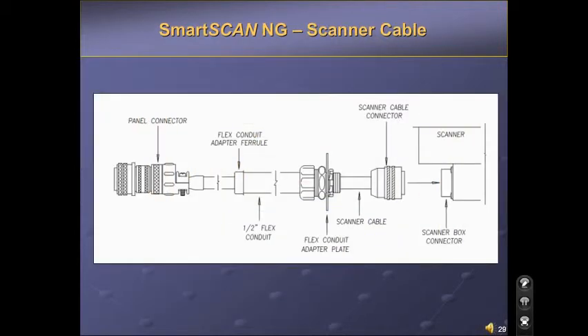These are the NG scanner cables. The cables can be purchased in any length. Our standard cables come in 65 feet, 100 feet, and 130 feet. Each cable comes complete with connectors on both ends that have been potted in a polyurethane compound.